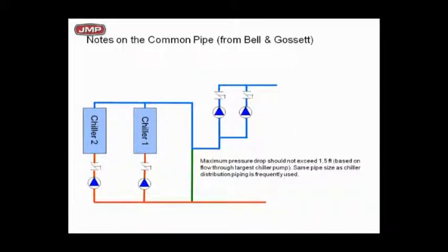Let's give you a real number. B&G's going to say try to keep your max pressure drop not to exceed a foot and a half or 18 inches. Very easy to do if you put two tees to keep it close together.